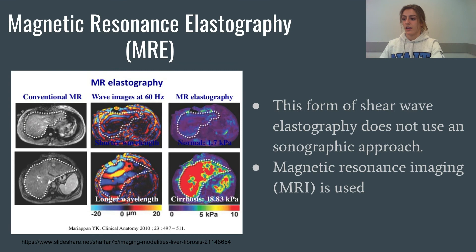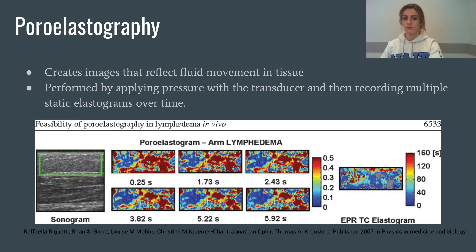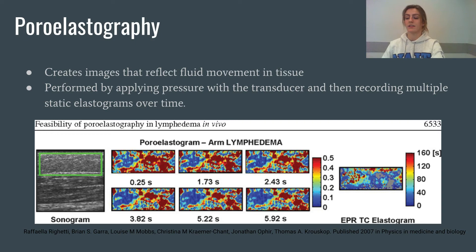Magnetic Resonance Elastography, or MRE, does not use a sonographic approach. MRI is used to generate shear waves within the body, save images of the propagation of the shear waves using MRE technology, and then process these acquired images to generate quantitative maps of tissue stiffness, or elastograms. Finally, we have poroelastography. Poroelastography creates images that reflect fluid movement in tissue — tissue is viewed as a porous substance that contains liquids. Pressure is applied with the transducer, and multiple images are recorded to produce multiple static elastograms over time. The Poisson's ratio is then calculated at every point in these images to show fluid movement. This method is still under experimentation, and lymphedemas are often used for this.